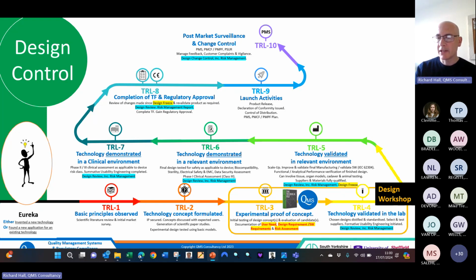TRL 5 is where you would take this verified and validated product and validate it in a manufacturing setting. It might just be increasing the jigs and fixtures of how you were creating it, and creating a more robust product so that every time you make a batch, it comes out exactly the same, validating that process and commissioning all the suppliers, validating software, etc. Then once you've done that, you can create some products and test them for safety testing, EMC testing, electrical safety, data security if you've got software, before then doing clinical performance studies.